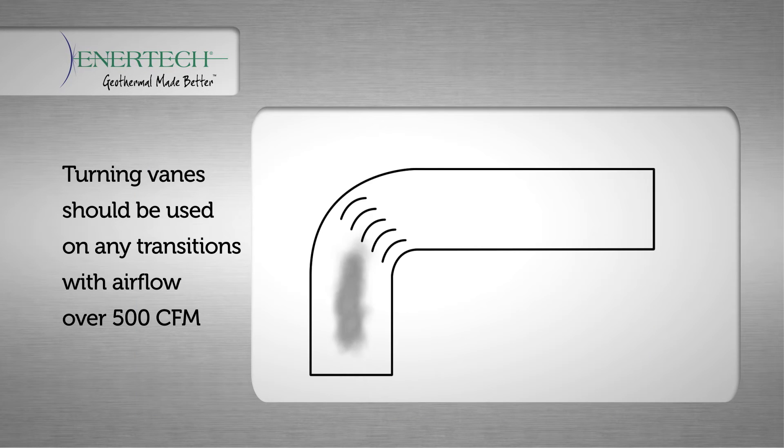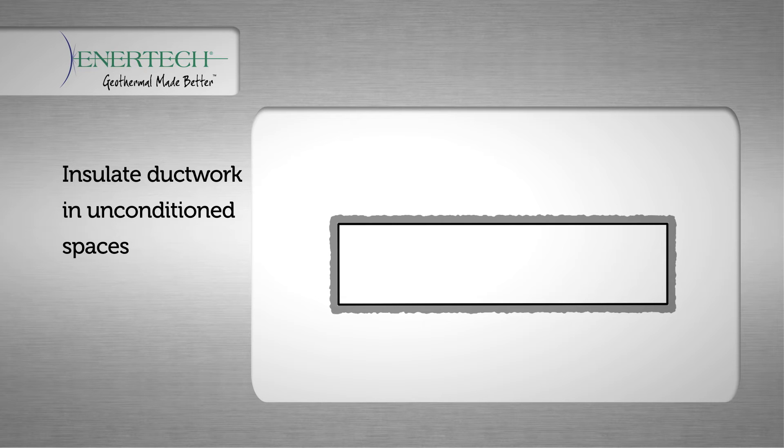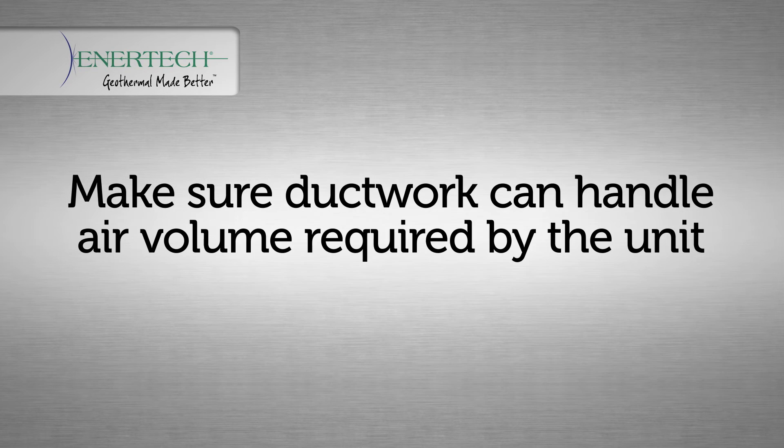Turning vanes should be used on any transition with airflow over 500 CFM. If the unit is installed in an unconditioned space, the metal ductwork should be insulated to prevent heat loss gain and to absorb air noise. If the unit is being installed with existing ductwork, the ductwork should be designed to handle the air volume required by the unit being installed.